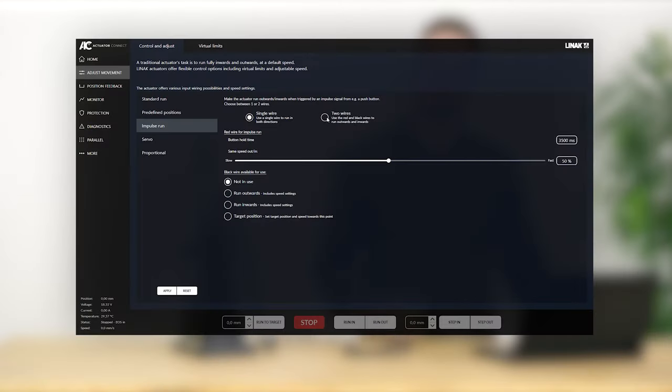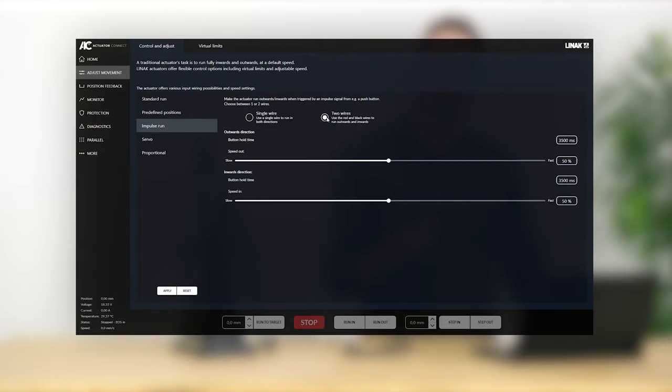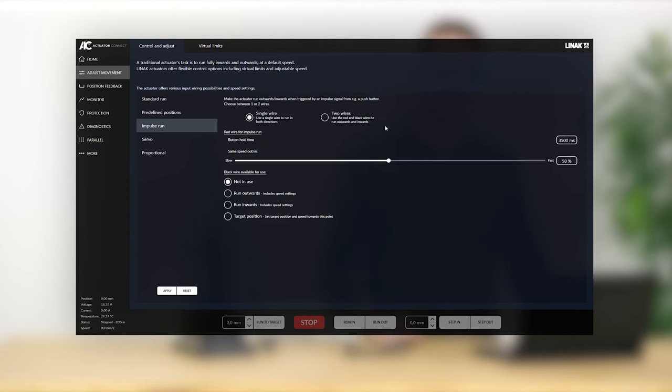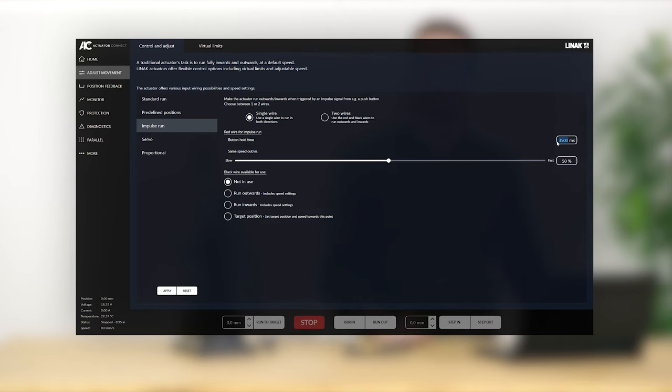For impulse run, either one or two wires are used to move the actuator. Impulse run is when a high signal is sent once but not held to request actuator movement to a specified point. If you choose impulse run on one wire, the actuator can run in both directions by giving a signal on this wire. As an additional feature, you can see that it's also possible to set the button hold time.